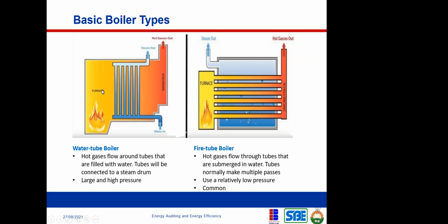Okay, and then you see the furnace is here, right? Before the hot gas that is coming out from this furnace passes through this tube, it will lose some of the heat to this water. Then it will go out here. This is the stack, the stack gas, the hot gases that go out. This is a lot of waste. So part of our energy efficiency measures will be how do we recover the heat that is going out from here? Mind you, the water coming in through these tubes will have collected some of this heat to turn into steam or hot water, whichever one you desire.